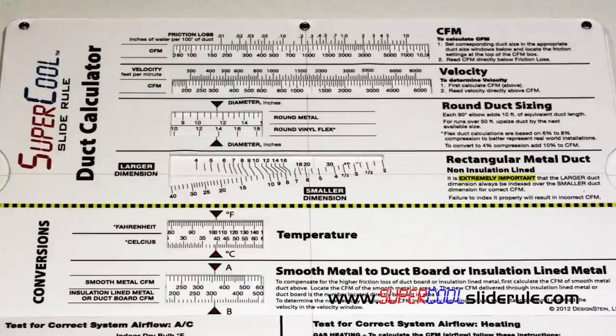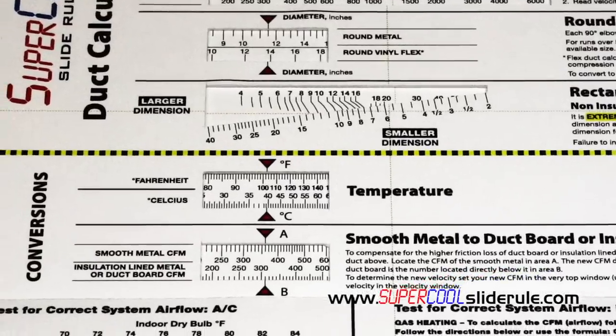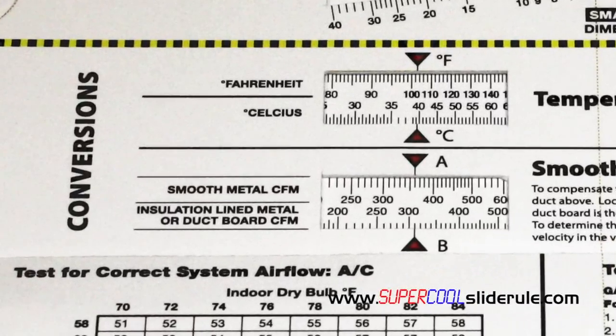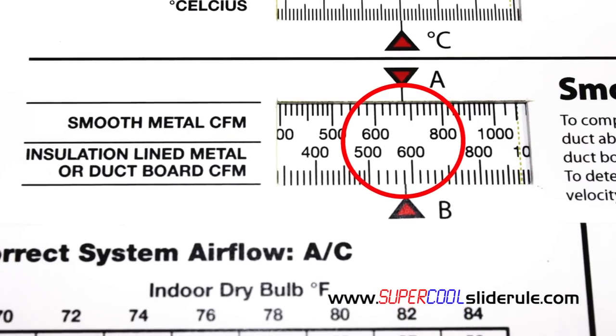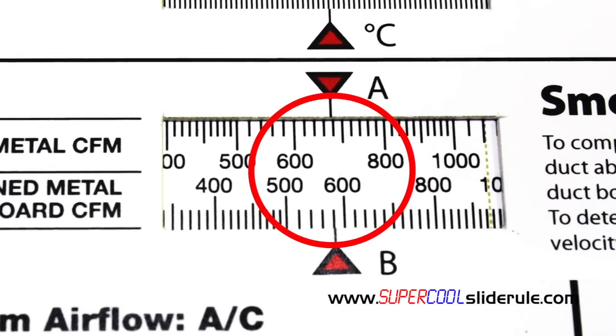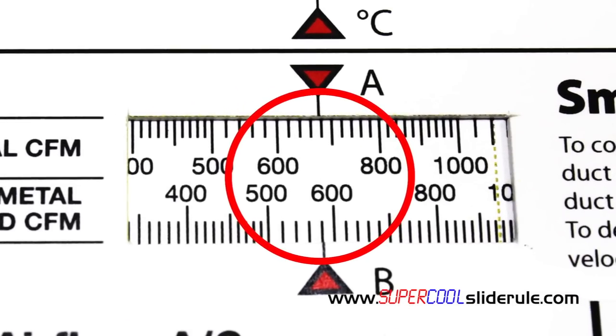Now let's suppose that in this application our insulation will be on the inside of the ductwork. Insulation lined metal has higher friction and lower CFM output than smooth metal duct, so we will need to use our conversion found right here. The super cool slide rule is the first tool to ever contain a direct reading conversion from smooth metal duct to insulation lined metal. To use this we simply set the smooth metal duct to 675 and check the corresponding number directly below it. In this example our number will be 580, so the CFM output of insulation lined metal will be 580.